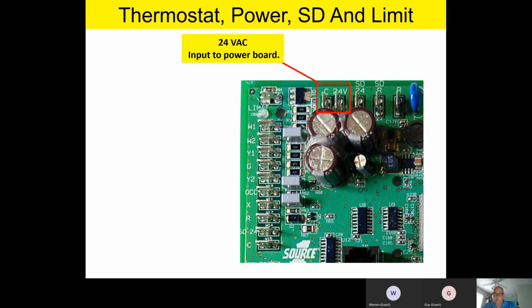And so that's the way our engineers have designed this. And I really like that, because now if you have a fault on the board, even though you're in a shutdown condition, you can still read that fault on the user display because we have power to the board all the time. Even in a shutdown scenario, we've got power to the board, so the microprocessor can still think and tell us what's going on. Any questions or comments on that?